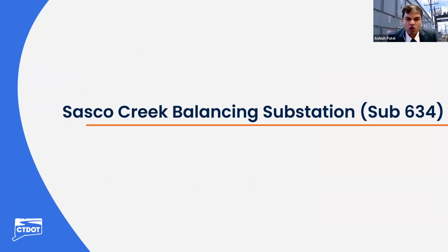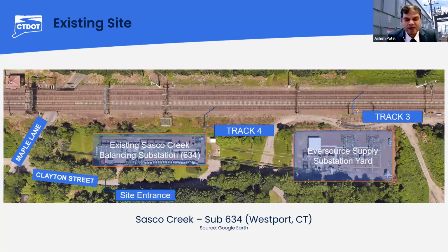I'll give a brief overview of the replacement of the Site 1 Sasco Creek Balancing Power Substation scope of work. The existing Sasco Creek Balancing Substation is off of Clayton Street in the town of Westport, Connecticut. As we can see on this Google image, the New Haven main line 4 tracks are shown on the north. The existing Eversource outdoor rated supply substation is shown on the east, and the existing Sasco Creek balancing substation is located on the south side of track 4, adjacent to Clayton Street. The project site entrance is also from Clayton Street.